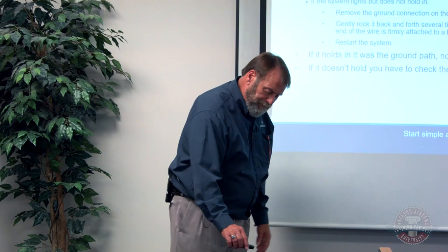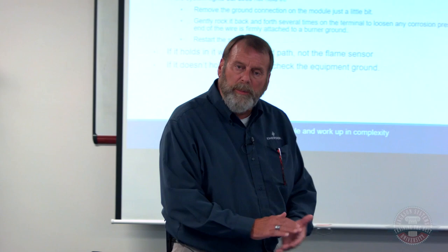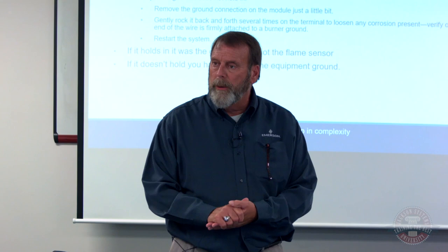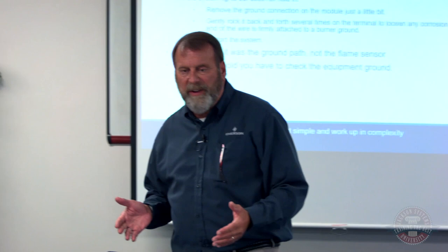Remember, I was out on that job with Ms. McGillicuddy, fired the unit off, and said, hey, it's a bad flame probe. I got to go and clean it off. So I moved everything out of the way and took out the flame probe. When I moved all those wires out of the way, what else do you think I moved? The ground wire, the little green wire that goes to the burner manifold.